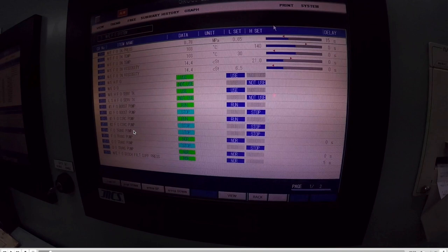And one problem that we get is that the fuel was necessary to heat up to 120 or 125 degrees, and it was really difficult in cold conditions. What we did, we used two heaters. Two heaters was quite enough to reach that temperature.